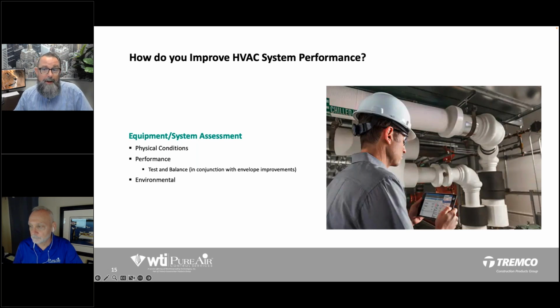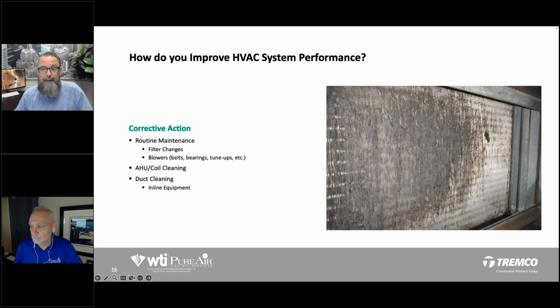And typically you would want this in a comprehensive report with recommendations to be able to start to make that 3-5 year plan to start to take that corrective action. And when we look at the corrective action, what are we talking about? We're talking about routine maintenance, being inside of these units, being able to change the filters regularly, make sure the blowers are operating properly, that the belts are at the right tension, that the bearings are greased, that you're doing regular tune-ups, so the blower is not cavitating, so the belt's not shedding rubber that could get into the coil or even downstream, right?